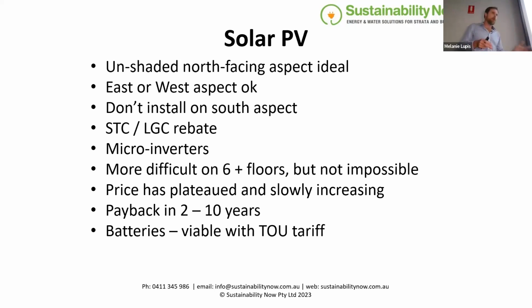One example I was involved with was a building with 5 apartments that had a really nice north-facing roof, just the right size for a 10 kilowatt system. We set up a big 10 kilowatt array and split it up using micro inverters, so each apartment got 2 kilowatts. It worked out quite well. You could have done the same thing with string inverters if you had room for 5 of them, but micro inverters are handy for that sort of setup.